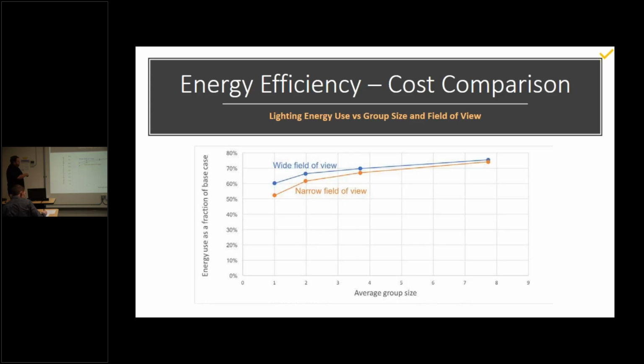And so here's kind of what that looks like comparing group sizes. If we do case-by-case basis, we're going to have a 51% energy consumption for the narrow versus 60% for the wide. And so for the narrow, it increases from 51 all the way up to about 73% if we're grouping it in groups of 8. So we see also a significant jump, but you see that as you get into the larger groups, the margin of difference between wide and narrow tends to become negligible. So at that point, if you know you're going to have large grouping sizes, you can basically save money and just go with the standard wide field of view rather than specifying the narrow field of view from the manufacturer.